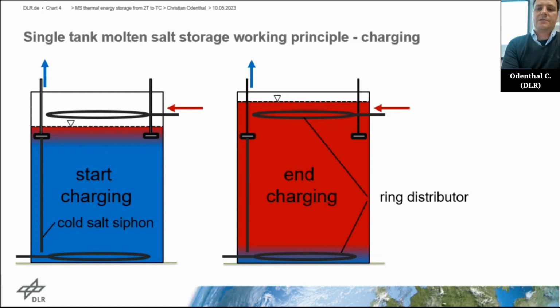Now, what we are looking at DLR is these so-called single tank thermal energy storage concept. And here you store the hot and the cold molten salt together in one single tank. And that is working because hot salt has a lower density than the cold salt. So the difference is quite high. It's about 10% in density difference. Because of that, you can have the cold salt on the bottom and the hot salt on the top. I always compare it with a latte macchiato. So there you also have cold milk and you put hot coffee on top and it remains stratified unless you start stirring it.